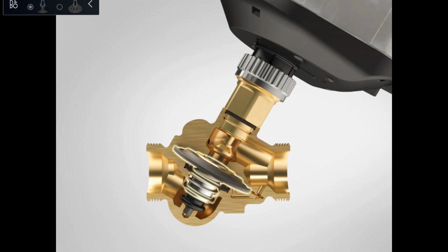It should not go to full close. If a DP, or differential pressure controller, of a PICV goes to full closed position, there is something wrong, either with the valve itself, it's faulty, or the maximum differential pressure of the valve is exceeded. Let's say your system pressure, pump head, is 6 or 5.5 bar, and the valve can take only 3.5. We will end up in full closed DP. And if you have a full closed DP, the valve will not work. And there are different scenarios. Sometimes it's hammering, sometimes it's leaking, sometimes it's whistling, sometimes it's having cavitation in the system. So it's really not recommended.